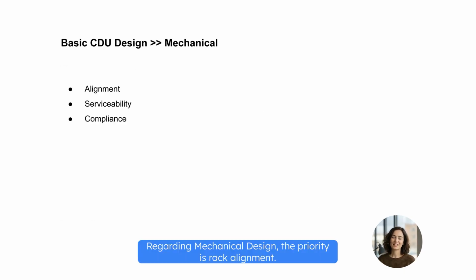Regarding mechanical design, the priority is rack alignment. The CDU's footprint must mirror standard rack layouts. This ensures we can scale the data center up or down seamlessly without layout conflicts. For operations, we require full serviceability. Access must be available via the front or rear doors. And finally, regulatory compliance isn't an afterthought. It must be integrated throughout the entire product development cycle.